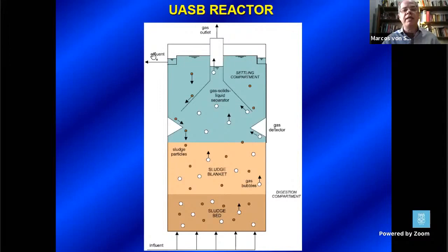Okay, these white dots here are bubbles of gas. Intense anaerobic digestion is taking place here. If these bubbles enter this compartment here, they would affect the sedimentation of the solids. We want good sedimentation of solids here. And then we have what is called a tri-phase separator. So three phases: gas, solids, liquid. It collects the gas, and you can use the gas later on.